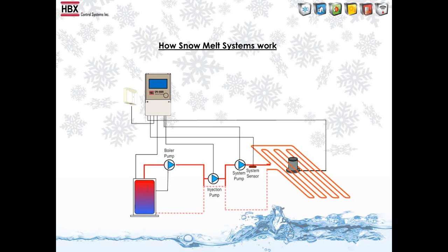So this is a basic injection system. We have the snow melt sensor out in the slab somewhere. We've got a system pump, an injection pump, and some sort of heat system. So we would start out at idle. When there is no snow detected, we'll set just an arbitrary number of 28 degrees. So when the system is idling, it's targeting this slab to be 28 degrees all the time. That's below freezing, so it doesn't cost $1 million to heat the slab all the time. But when you do use an idle temperature of 28, it will recover fairly fast. So it won't need a lot of time to go from idle into melt mode.